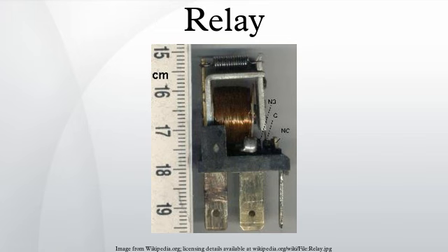Where the overload relay is exposed to the same environment as the motor, a useful though crude compensation for motor ambient temperature is provided. The other common overload protection system uses an electromagnet coil in series with the motor circuit that directly operates contacts. This is similar to a control relay but requires a rather high fault current to operate the contacts. To prevent short overcurrent spikes from causing nuisance tripping, the armature movement is damped with a dashpot.